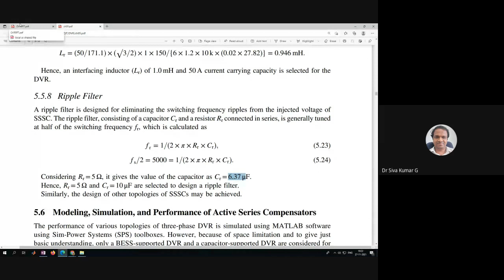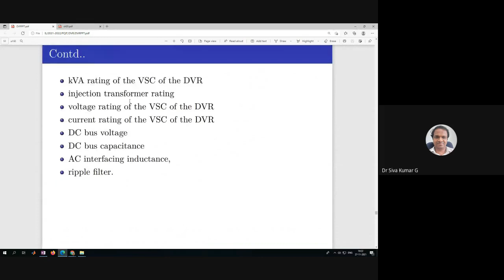If the value of the resistance is higher, the more the losses will be there. In that case, the inverter has to supply the losses. Typically, considering R as 1 ohm, or even a still lower value, is good to reduce the switching losses. Yeah, these are some of the design aspects of a dynamic voltage restorer.